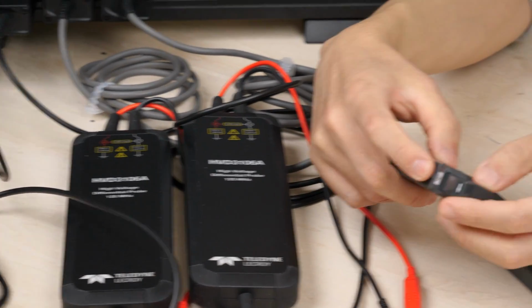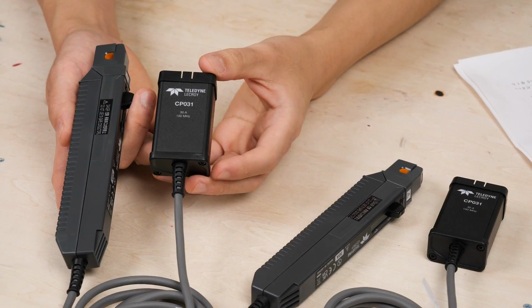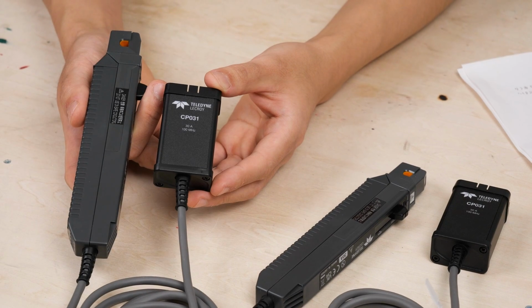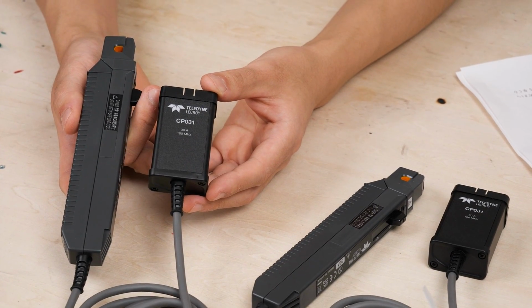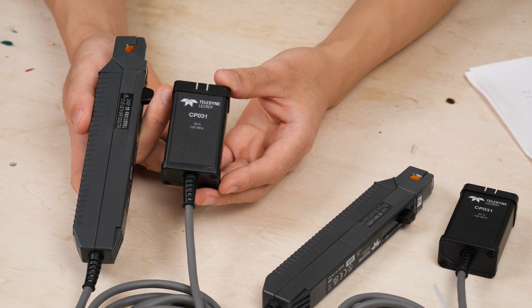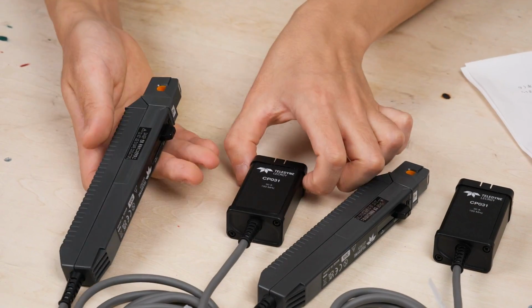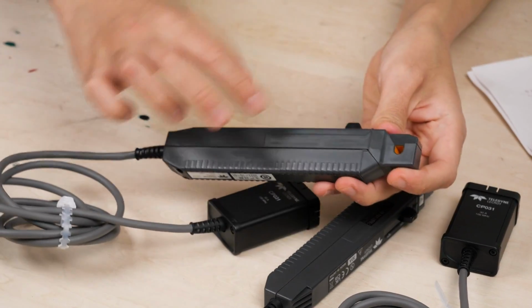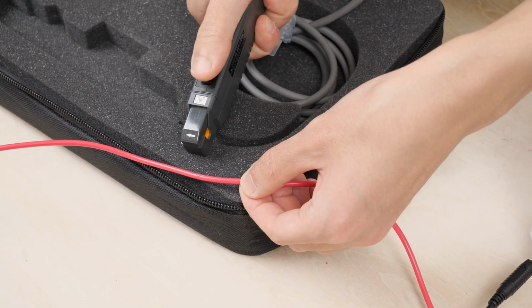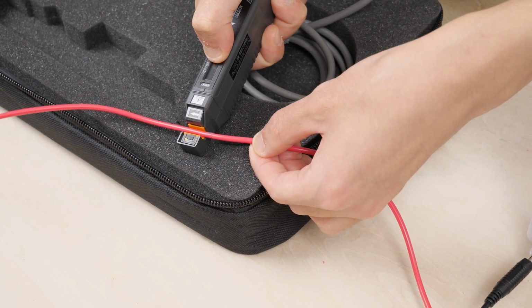These are current probes, clamp-on type — CP031 models. The effective value is 30 amperes. They're Hall effect probes, so they can measure both AC and DC. You measure the signal by clamping a cable at the tip of the probe. This clamping part is made by Hioki Denki, who makes this part for many manufacturers' probes.